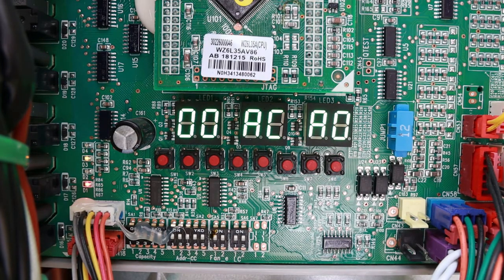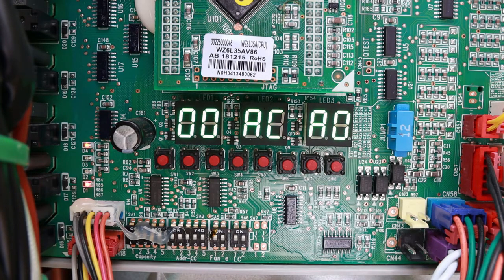When you power up the system for the first time, this is what you're supposed to see on the LEDs: 00 AC AO. AO means the system hasn't been commissioned yet, so it's time to start the commissioning cycle. It's important to keep in mind that you're supposed to see this AO on the LEDs of the evaporators as well as on the display of the controllers. We want to see AO on every unit so we know the whole system is ready to be commissioned. If AO is missing from any unit, you have to go check what's going on and fix it before proceeding. So go back inside and check the units.